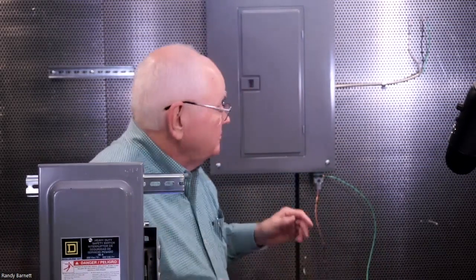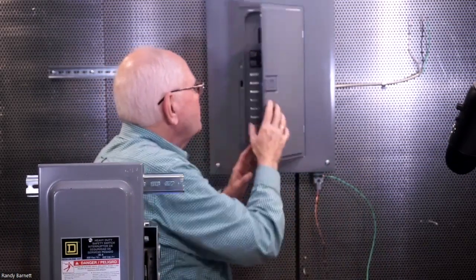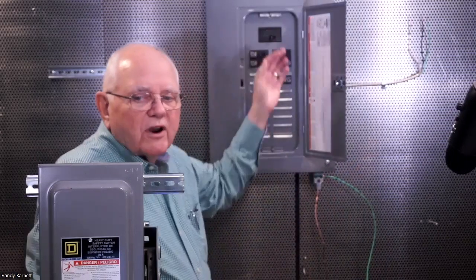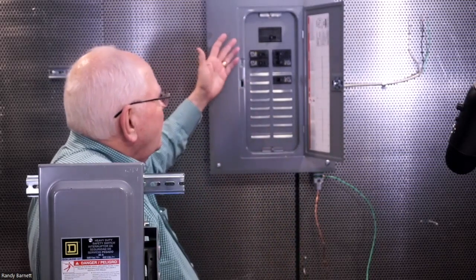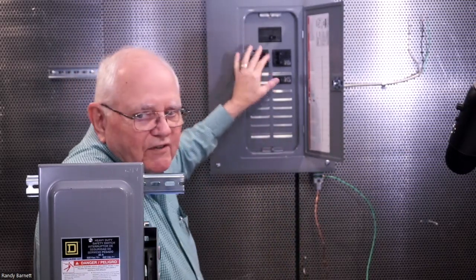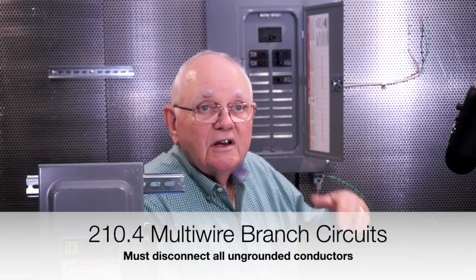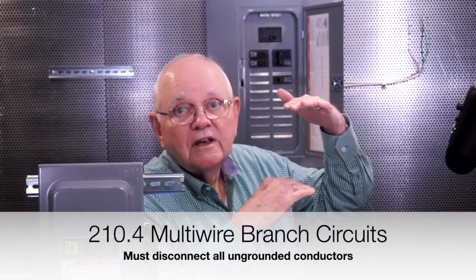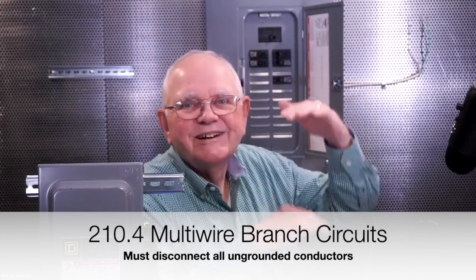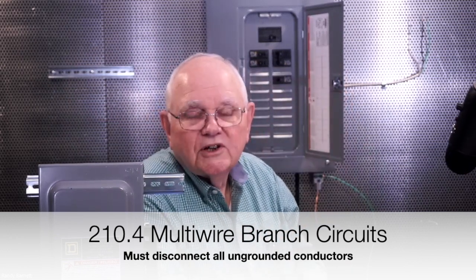Now, I can use other things as disconnecting means, right? For instance, I can go inside of my panel board. And of course, I've got a main breaker up here at the top. That's my disconnecting means. I've got requirements. For instance, I've got two separate molded case breakers that I can use to supply a duplex receptacle, right? Break that little tab off on the hot side of that duplex receptacle, separating the top from the bottom. What I've got is a multi-wire branch circuit then.